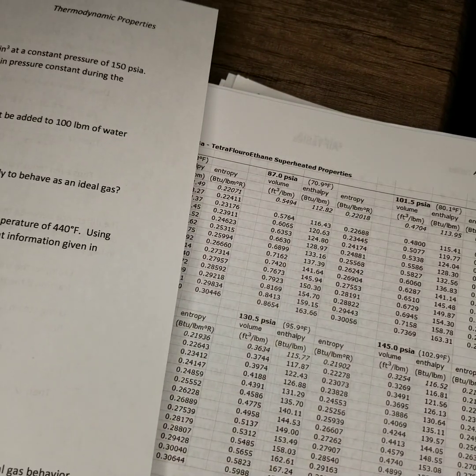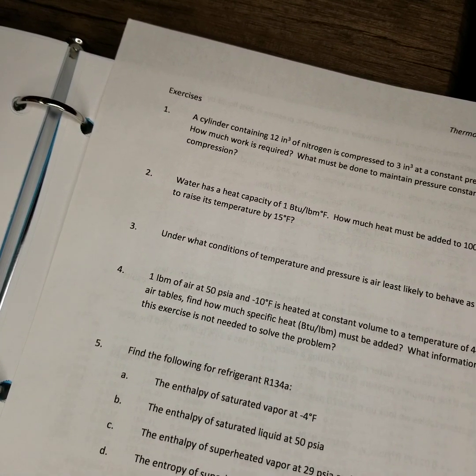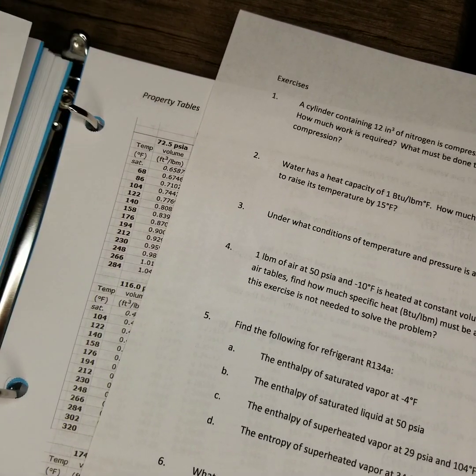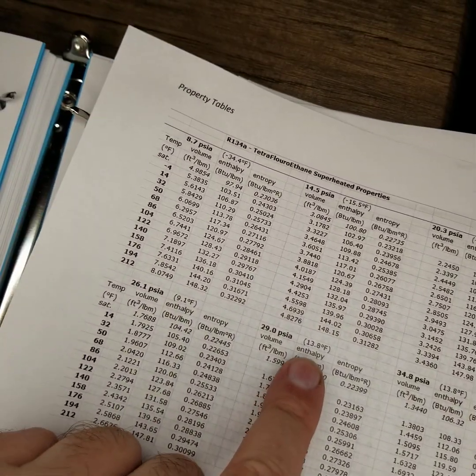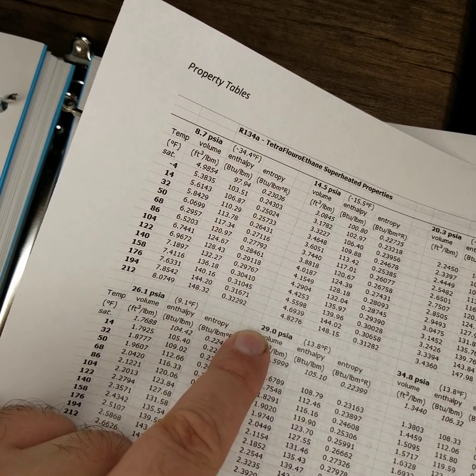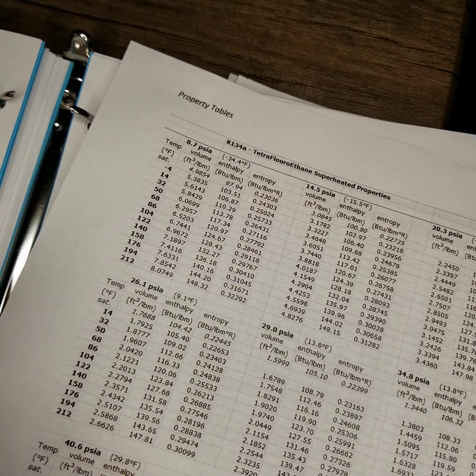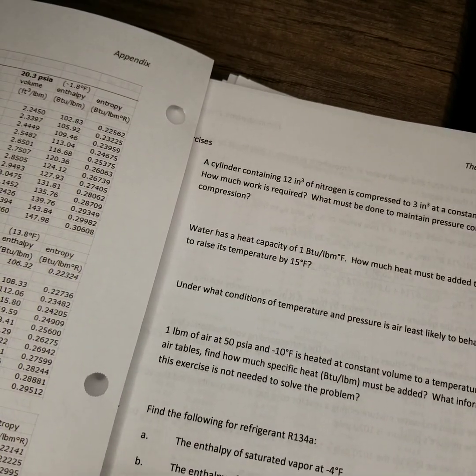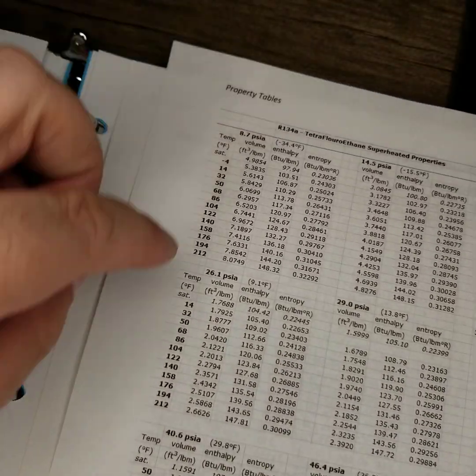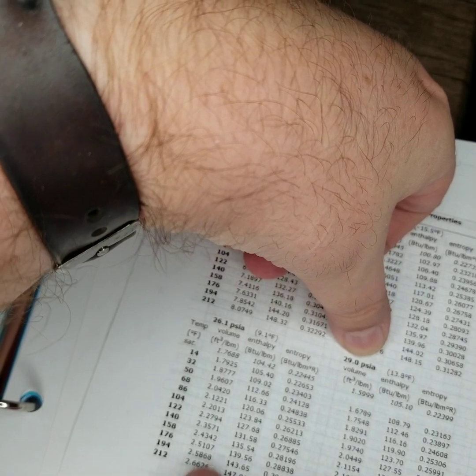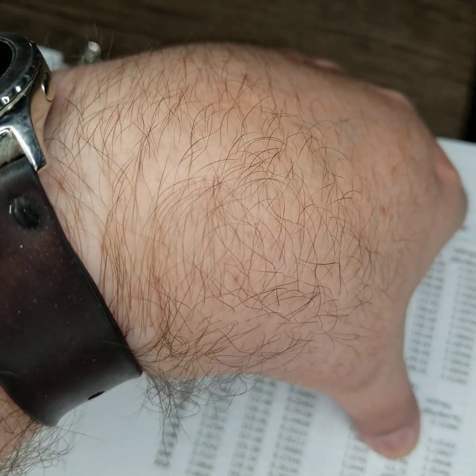So enthalpy of a superheated vapor at 29 PSIA. I'll bring this page here over. The enthalpy of a superheated vapor at 29 PSIA. And that enthalpy is, does it give us a temperature? Oh, and 104 degrees. So 29 PSIA here and 104 degrees Fahrenheit. And it's asking for the enthalpy. So 123.70 BTUs per pound mass.